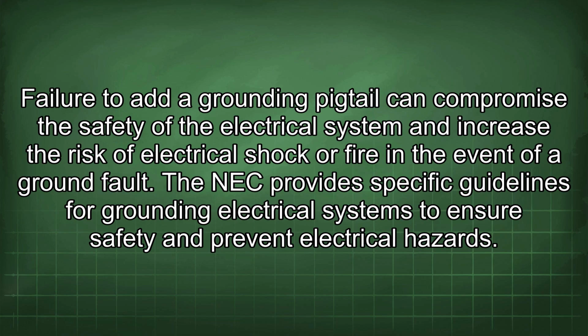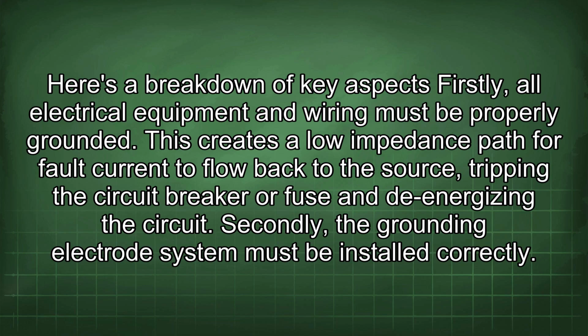The NEC provides specific guidelines for grounding electrical systems to ensure safety and prevent electrical hazards. Here's a breakdown of key aspects. Firstly, all electrical equipment and wiring must be properly grounded. This creates a low impedance path for fault current to flow back to the source, tripping the circuit breaker or fuse and de-energizing the circuit.